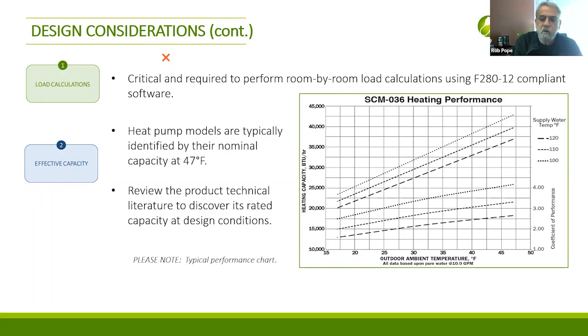The outdoor ambient temperature goes down, and so does the capacity. If you take the performance curves of every one of those heat pumps, they'll all be a little different. Some will be a lot better than others. But nevertheless, you don't know how that unit's going to perform until you dig in and check the performance curves of the unit. And that's critical. You need to know that to size the equipment in the first place. What size of equipment am I going to put in the house? And after you size that equipment, you need to know what kind of backup heat or auxiliary heat I need, and when do I need that to come on? How much of it do I need?